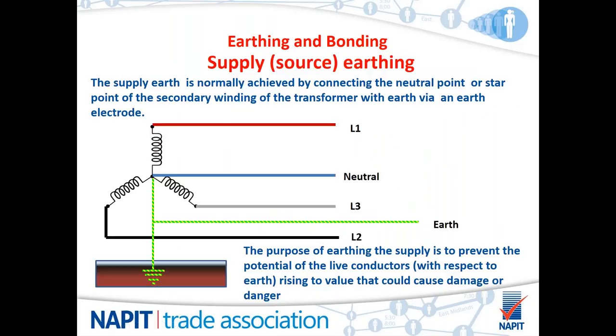Where does the earth come from? The earth comes from the supply source. The supply authority's transformer, and the secondary side is depicted in front of you. The windings are so arranged that they form a star connection. The middle of that connection is always 0 volts. No matter what, it will always be 0 volts, and to keep it at 0 volts, the supply authorities install a large plate underneath the concrete plinth of the transformer substation, and a tape from that plate is then taken and bolted to that star point.